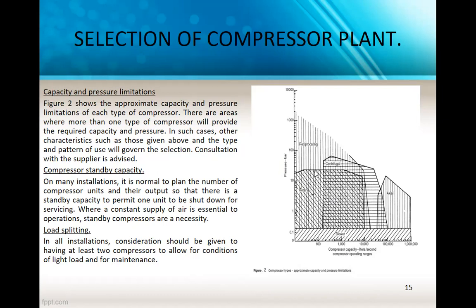Ang pressure mo is nasa, this is a logarithmic scale. So ito log scale, ito log scale din. Okay? This is 10, 20, 30, 40, 50, 60, 70, 90, yan. So 20, 10, 20, 30. So 30 psi, tapos 1,000. So dito ka tumapat. So ang pipiliin mo is centrifugal or the reciprocating. Kasi pareho sila pumasok yan. Okay? Sample lang yun.